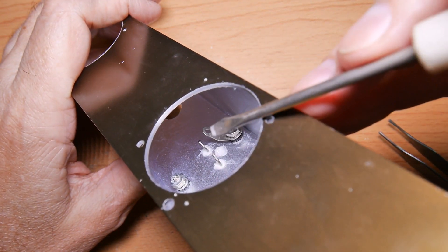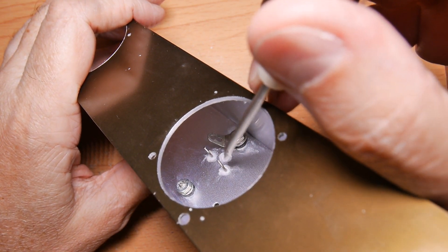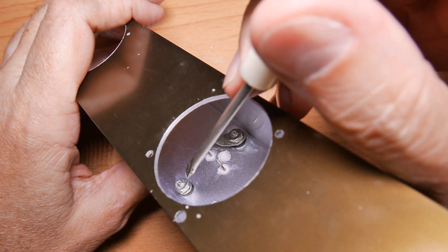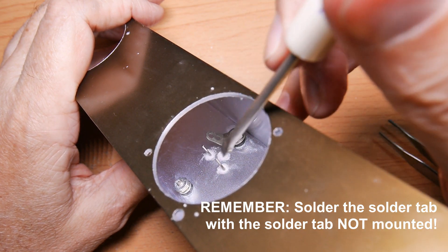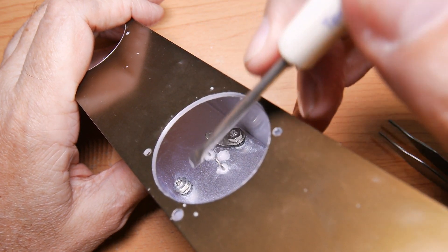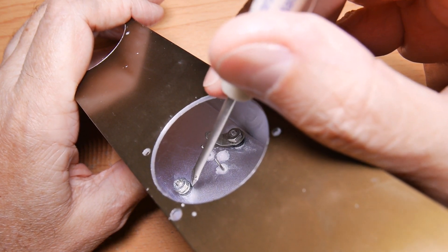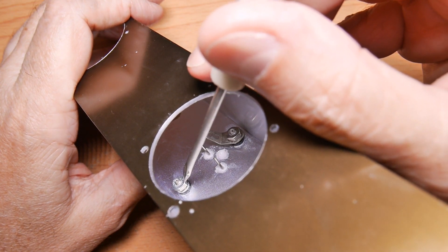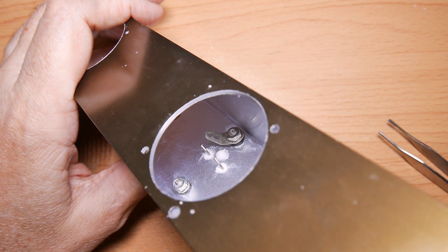Let's take a look inside. On the other side, we can see that, first of all, that our contacts are fairly well centered inside those holes, that's very important. It also indicates that we probably have the end hardware in position correctly. So yeah, that's important. And the other thing is to make sure that these nylon insulators are down in position. These are black. They also come in white. Make sure those are in position. They appear to be from here. Let's take a look from the other end and make sure that's the case.